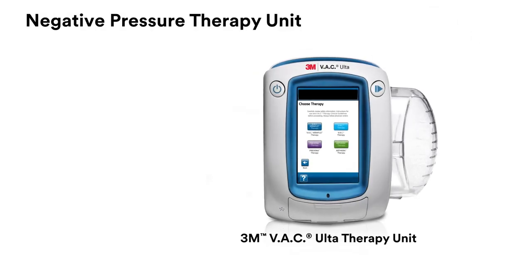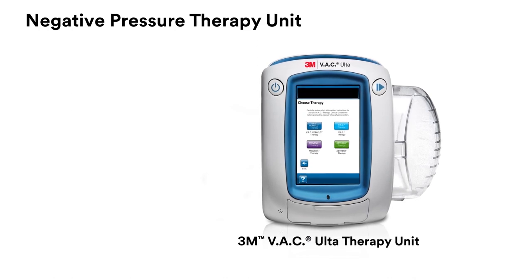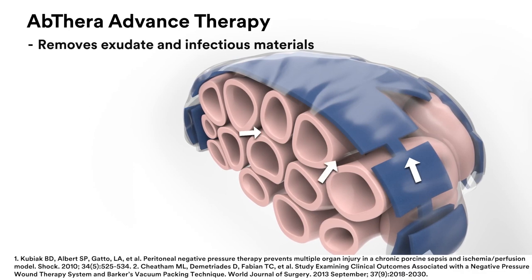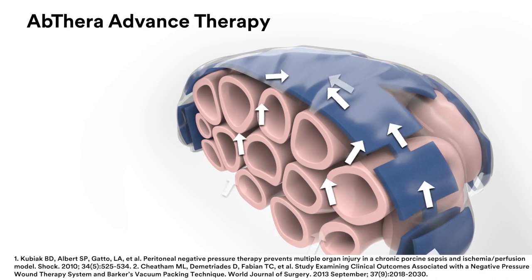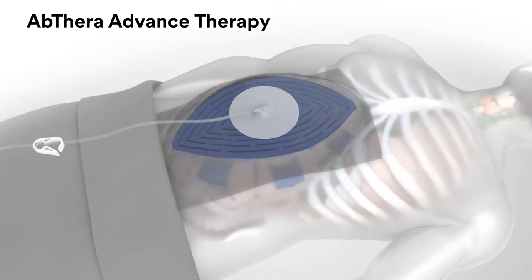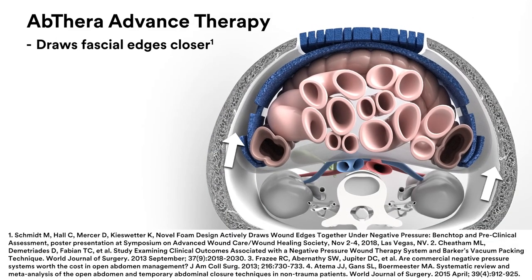The 3M VAC Ulta Therapy Unit applies continuous negative pressure to the AbThera Advance Dressing. This process removes exudate and infectious material throughout the abdomen and in the paracolic gutters, helping reduce edema. At the same time, the perforated foam and the encapsulated foam within the visceral protective layer collapse medially, drawing fascial edges closer together.